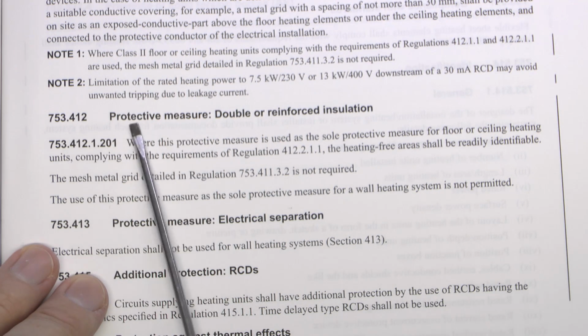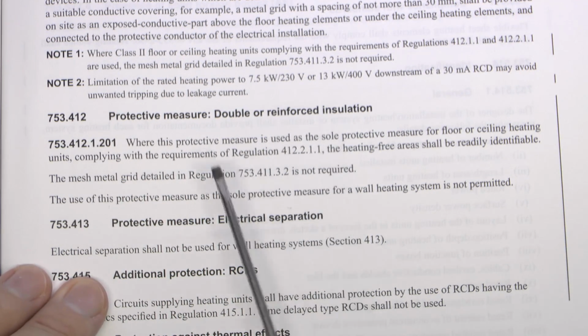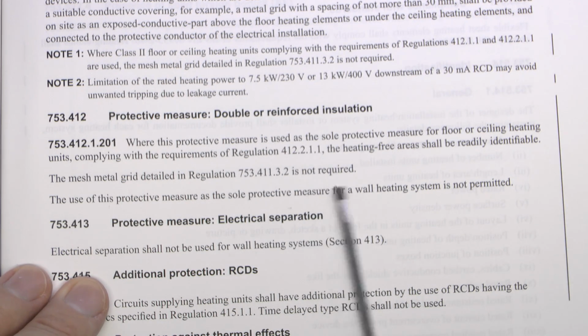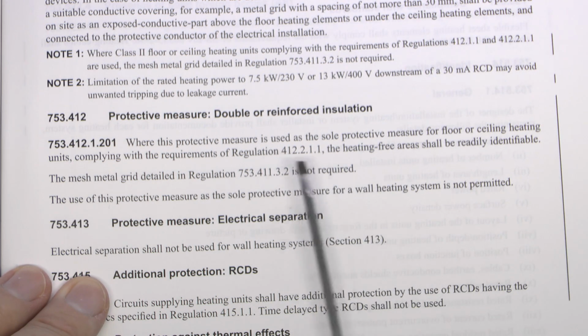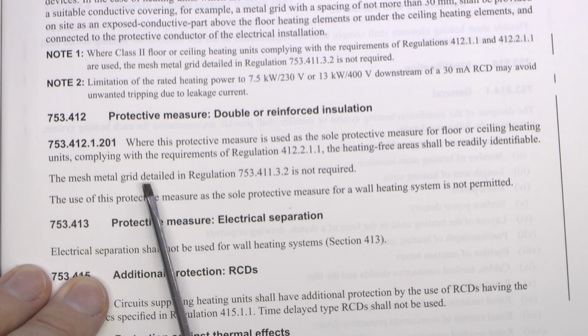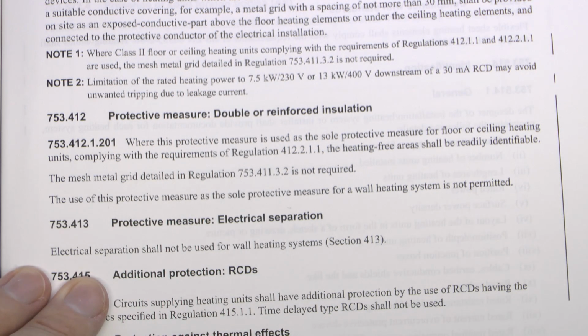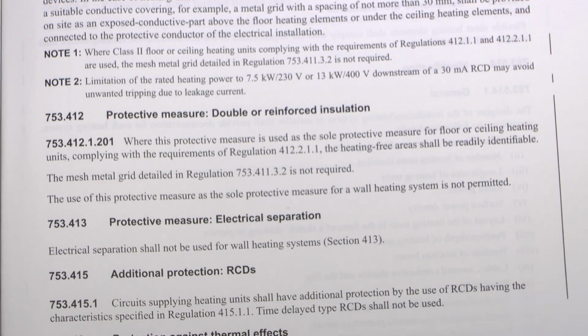753412, which is this one here, protective measure of double or reinforced insulation. This is all new, so it's been added in there. So again, it's about the items described there, and it goes on about the metal mesh grid as previously mentioned. The use of this protective measure as a sole measure is not permitted if you're going to have a wall heating system, only of course for the floors and other items.